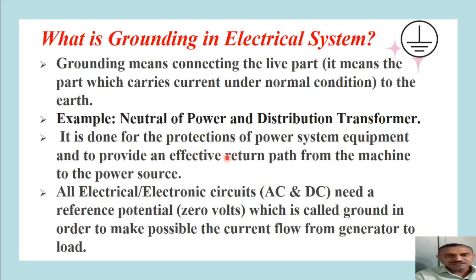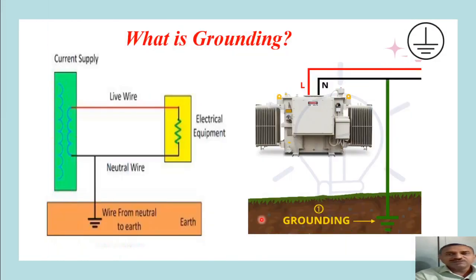By means of grounding, that is connecting the neutral of power and distribution transformer to the earth, we are providing an effective return path from the machine to the power source. Now we know that all electrical and electronic circuits, whether they are AC or DC, need a reference potential, and that is 0 volts, which is called ground, in order to make current flow possible from generator to load. That reference 0 potential is possible by making the neutral of the system connected to the earth. It ensures that the voltage of the neutral at the point of connecting it to the earth will be 0, but it may not be 0 over the whole of its length, because when the neutral is carrying current, there will be voltage drop.